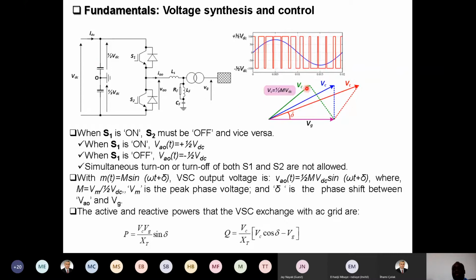And changing the magnitude of the voltage here will also define the amount of Q. So based on these equations, if we change, for example, this point, it corresponds to leading power factor in this region, and this one to unit power factor. At this point you operate at 0 Q, this component equal to this component, so Q is 0. And at this point, this one is bigger than that, so this one is positive, so the reactive power will be from the converter to the grid. In this situation, because this one is smaller than the grid voltage, the reactive power will be from the grid toward the converter.